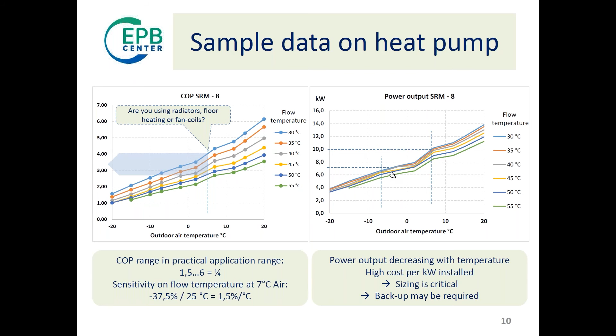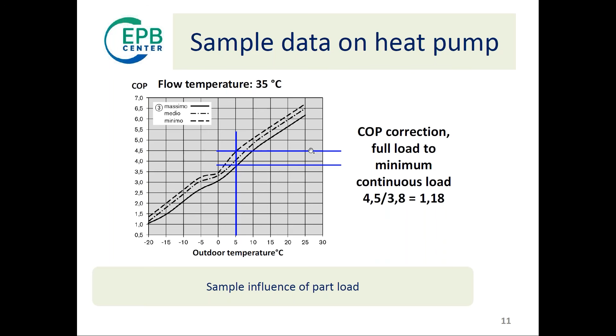And here again, we have the performance map of a heat pump. It's for one flow temperature. You have the performance COP depending on outdoor temperature, and you see the full load and part load characteristic. And you see that the same heat pump in the same operating condition has about 20% difference from maximum to part load. So that is another influencing parameter we have to take into account. So given this, what is the answer by the EN EPB standard?